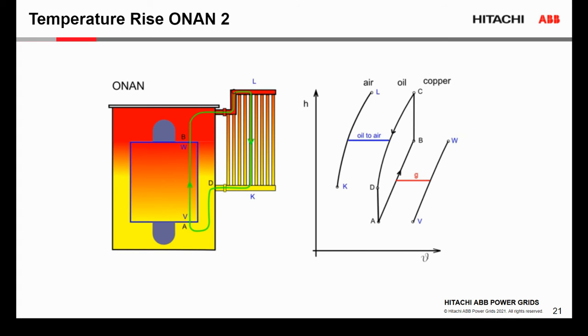And by changing the location of the radiators, we can improve the heat exchange between the radiators and the air. So this will reduce significantly the oil temperature in the tank. And with this solution, we can reduce the size of the cooling system. However, in some cases, we have to be careful because this solution is very sensitive to the location where we have high seismic activities, and it could be very difficult to provide sufficient bracing for high seismic accelerations.